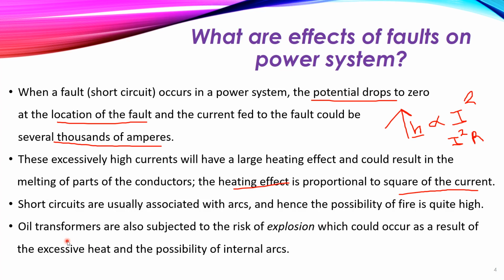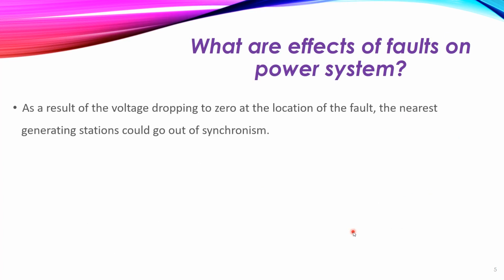Also, the oil transformer is subjected to the risk of explosion, which could occur as a result of excess heat and the possibility of internal arcs due to the breakdown inside the oil itself. So the oil transformer in this case will be considered as a bomb if we allow the short circuit current passage.